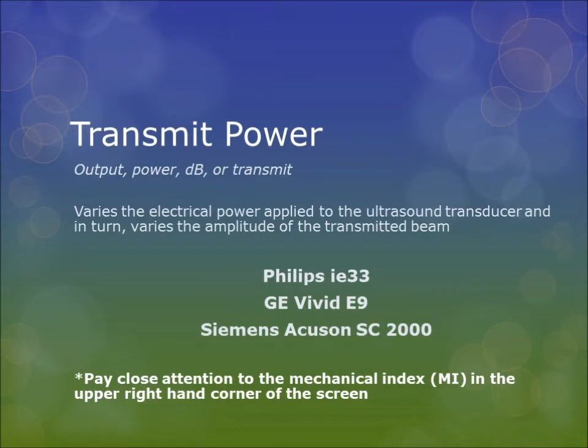Transmit power, also known as output, power, decibels, or transmit. The transmit power varies the electrical power applied to the ultrasound transducer and, in turn, varies the amplitude of the transmitted beam. You will see the transmit power demonstrated on the Philips IE33, the GE Vivid E9, and the Siemens Acuson SC2000.